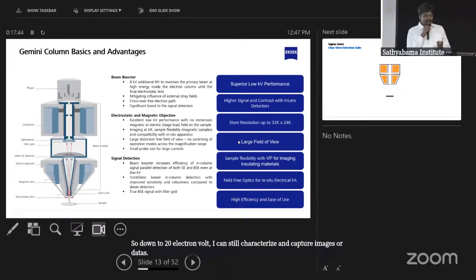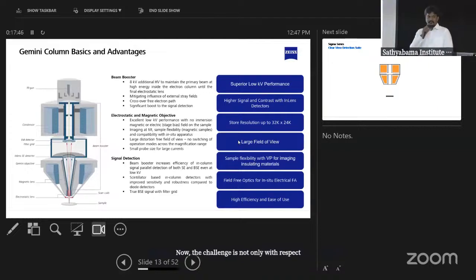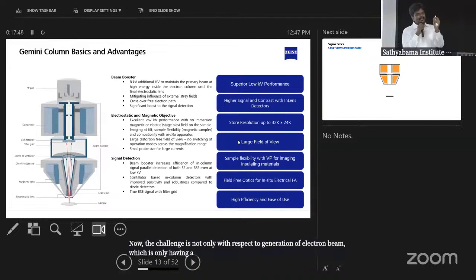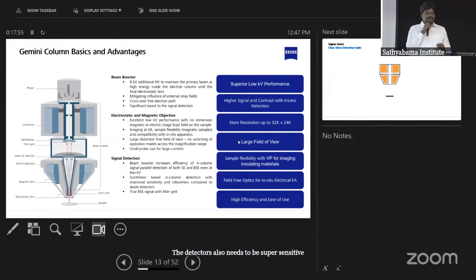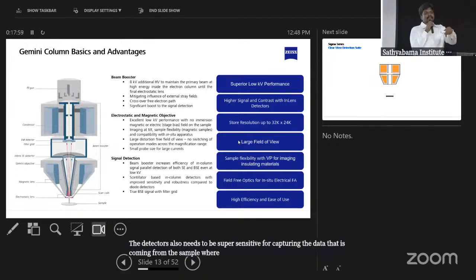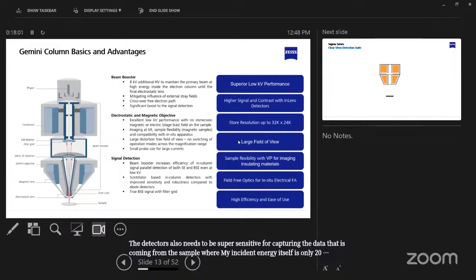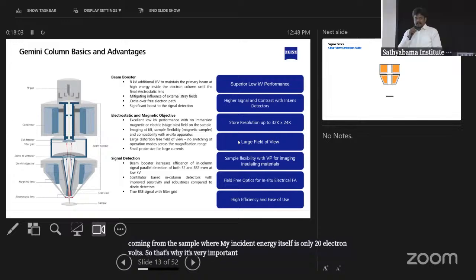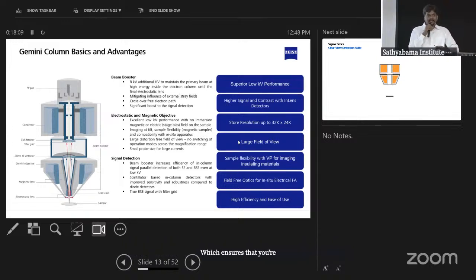Now, the challenge is not only with respect to generation of the electron beam, which has only 20 electron volts of acceleration voltage. The detectors also need to be super sensitive for capturing the data that is coming from the sample, where my incident energy itself is only 20 electron volts. So it's very important we have the most sensitive and robust detecting mechanisms, which ensure that you're not compromising on the data that you're capturing using your electron microscope.